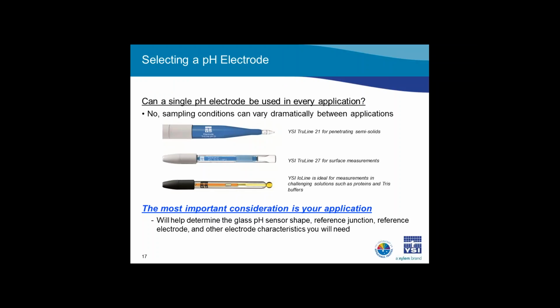Now, all of the information we just covered can be used to help you select the best electrode for your application. Now, a common question asked is if a single pH electrode can be used for every application. The answer to this is no, because sampling applications and requirements can vary dramatically between applications. As an example, measuring in meats and cheeses will require a spear tip sensor, while surface measurements require a flat sensor. If measuring in tris buffer, an electrode with a metal-free reference is required.